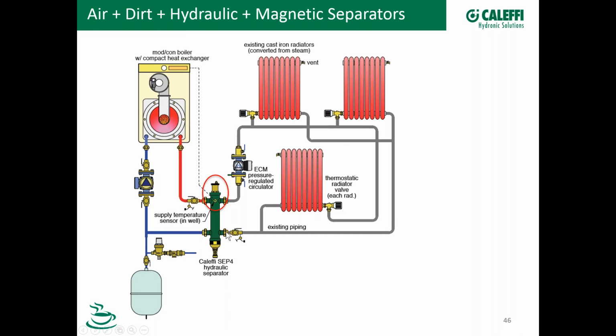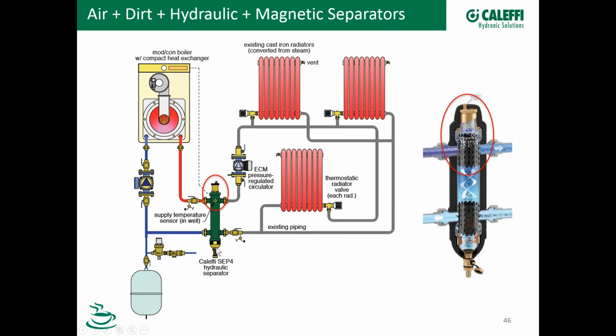Down below we have the dirt separation. We have a coalescing element down here as well. I'll show you what that looks like. That's scrubbing out the dirt. We have the magnet on this small one. The magnet is a snap-on collar, and we have the dirt coalescing going on down here and the air coalescing going on up here. So again, a very efficient product, right? With 4 connections, you get everything you need with hydraulic, air, and dirt, plus the added benefit of magnetic. And again, we still have our vents, right? We always have our high point vents.